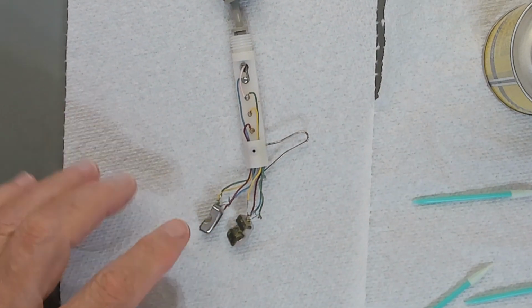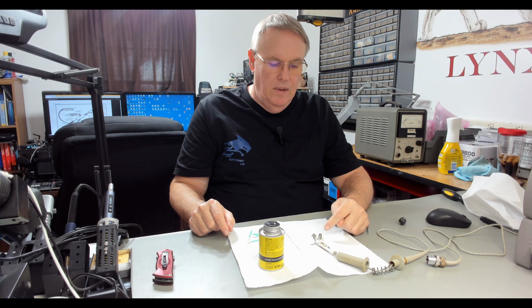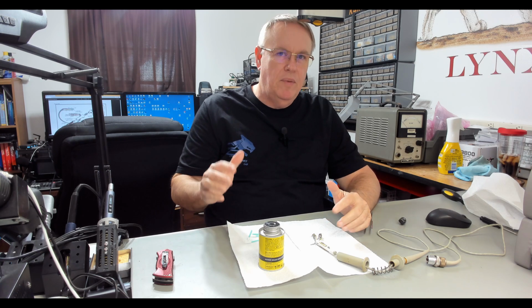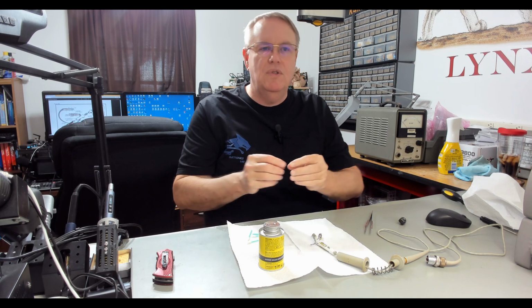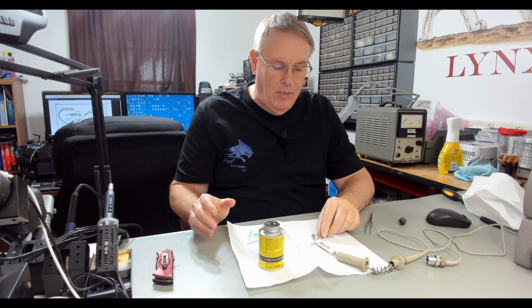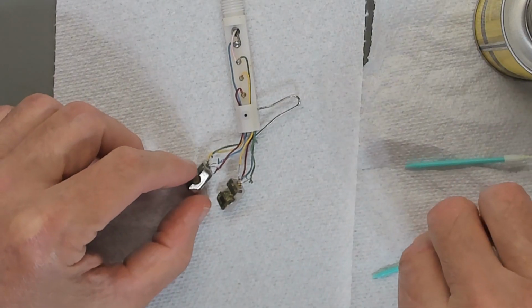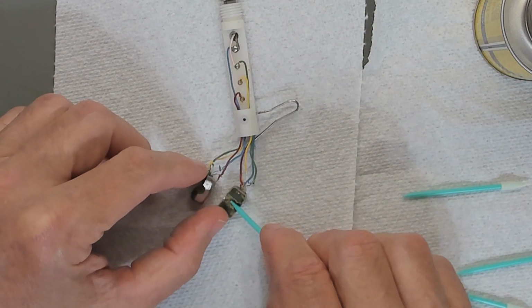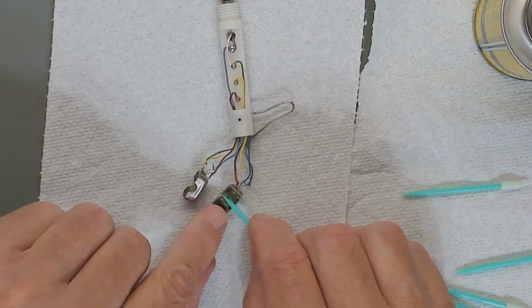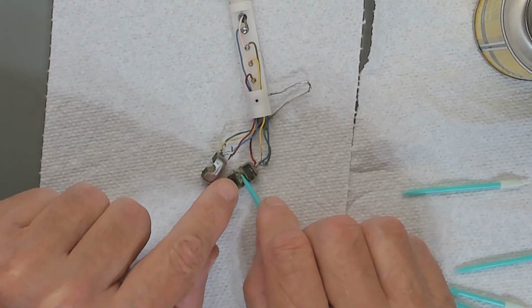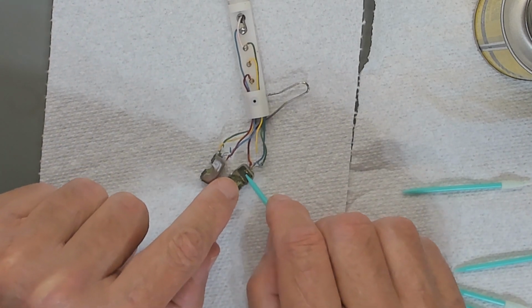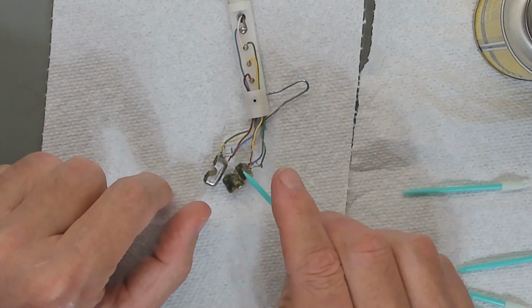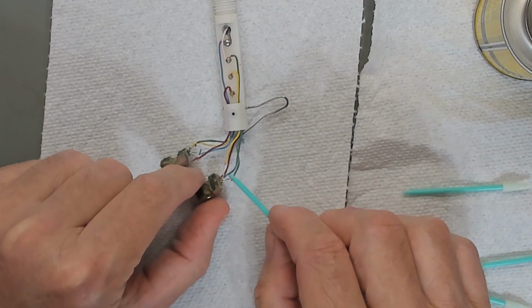And all I can figure is this probe has got in some chemicals. I don't know if somebody tried to clean it with something, or maybe it was stuck and they were trying to get, I don't know what happened, but it softened some of the very surface, if you can see here, of the potting material and glued the sensor together. And it ate the insulation on these wires.